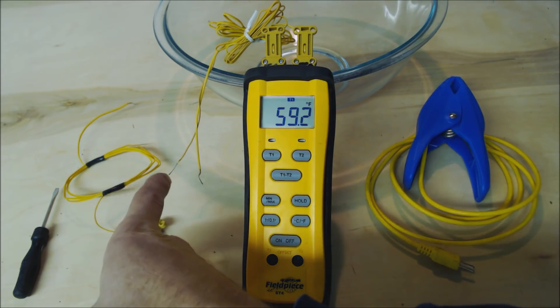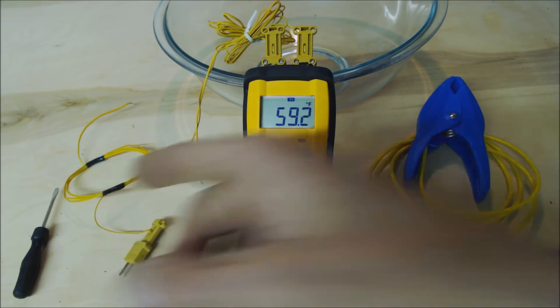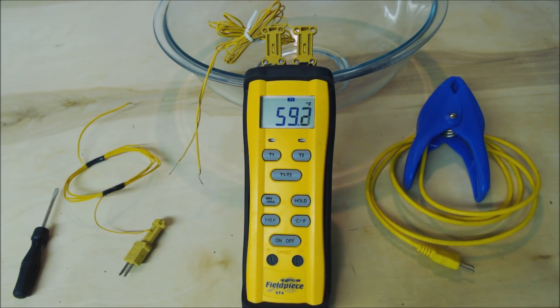We mount these on the suction and liquid line for superheat and subcooling measurements with our refrigerant gauges, and we also use the temperature meter for reading Delta T across the indoor evaporator coil for cooling. For conventional systems it's typically around 18 to 21 degree Delta T. We also use Delta T temperature measurements across the gas furnace or oil-fired furnace to take our temp rise.